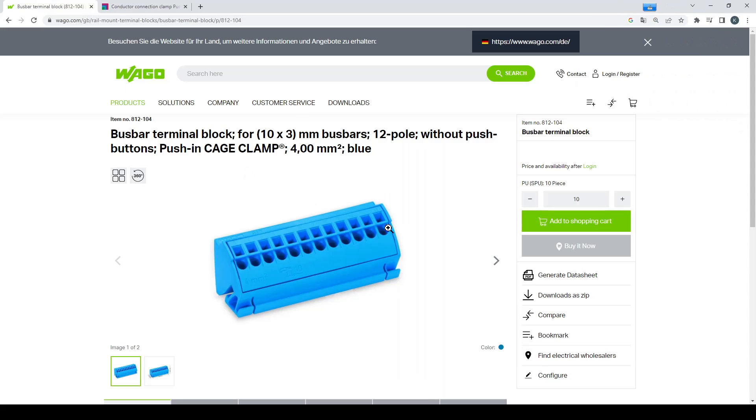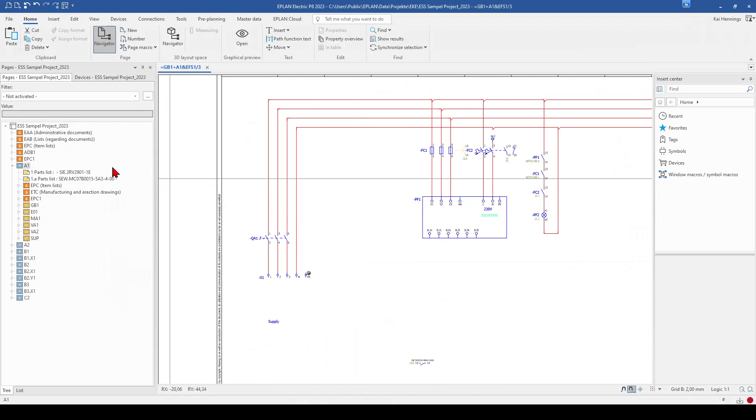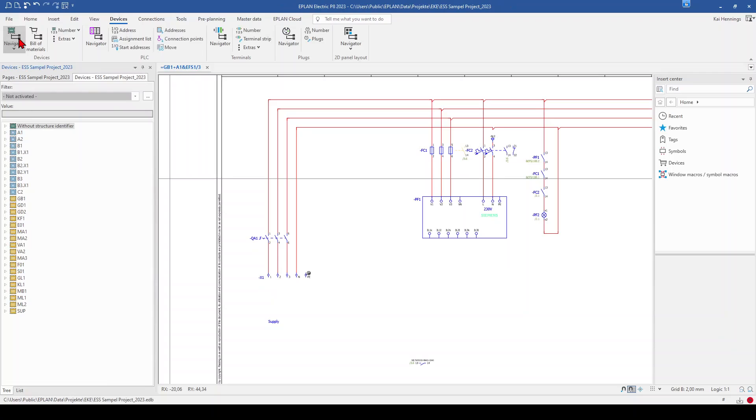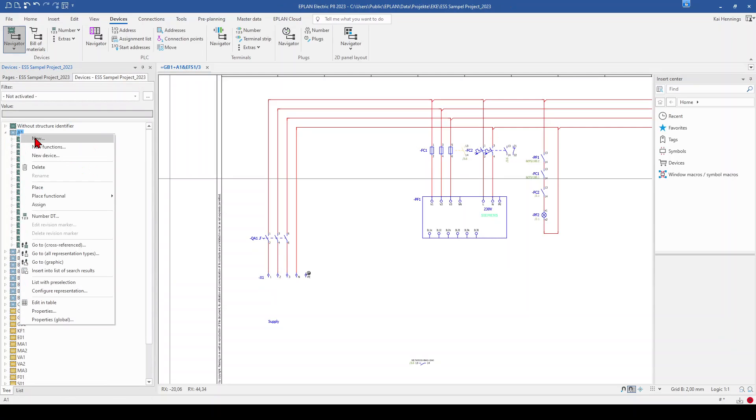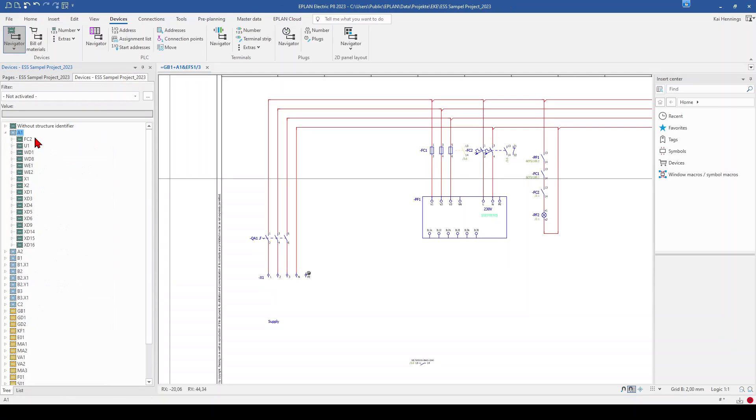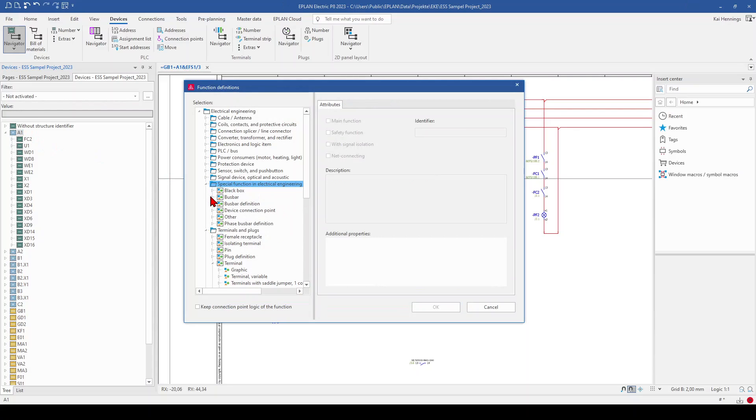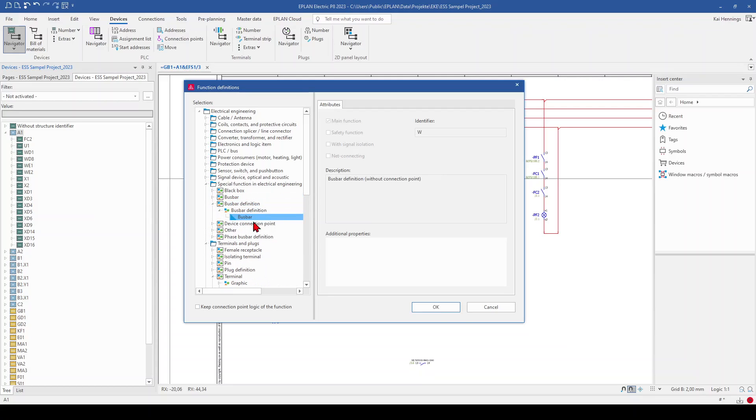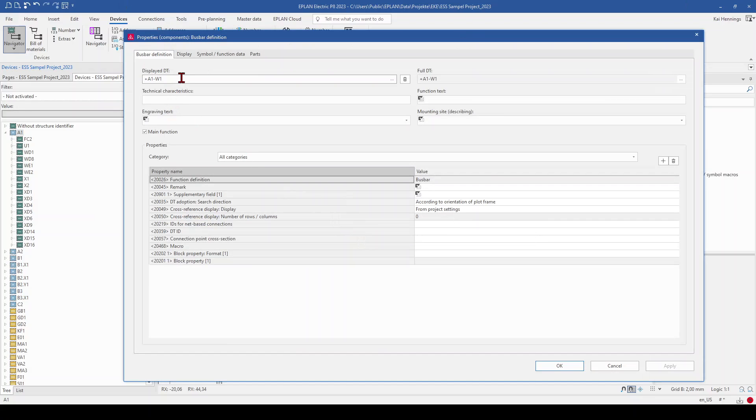And now we have a look on what we can do when we use such a busbar terminal block with 12 poles. So when we know already that this has 12 connections, we can go to our device navigator. So device and navigator. Go to our control panel A1. And here we make a right click and click on new. And now we first create a busbar definition. This should be for the neutral. We can also give a text here. Click OK.